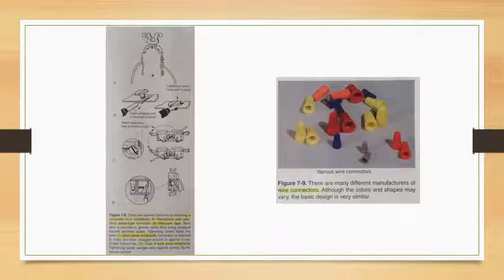Splicing conductors. Splicing is the process of connecting one wire to one or more wires. When done properly, the splice will last for years without any maintenance. An improper sloppy splice may disconnect as soon as you let go of the wires or worse yet, may come apart when the wires are energized. This can cause a fire, injury, or death. The NEC requires that all bare wire must be taped with insulation at least equivalent to the thickness of that of the conductor's original coverings.